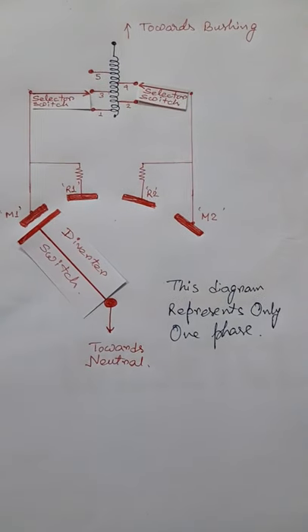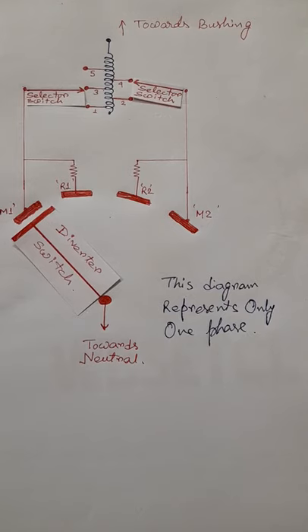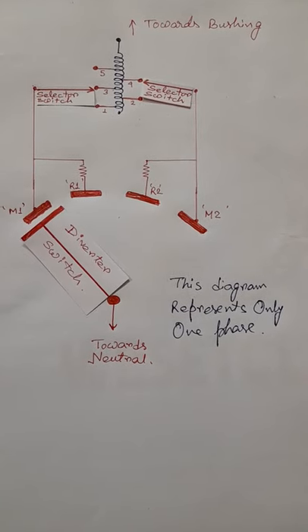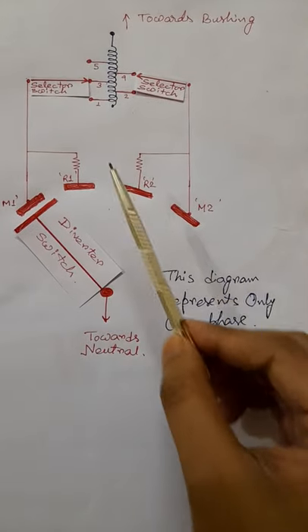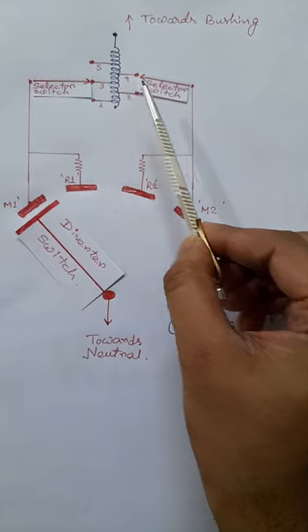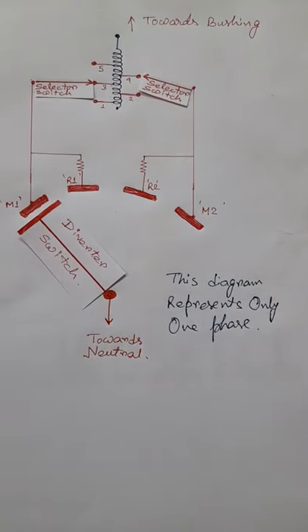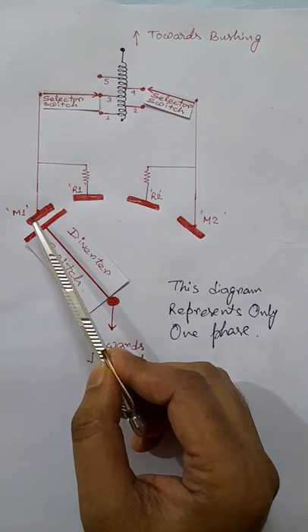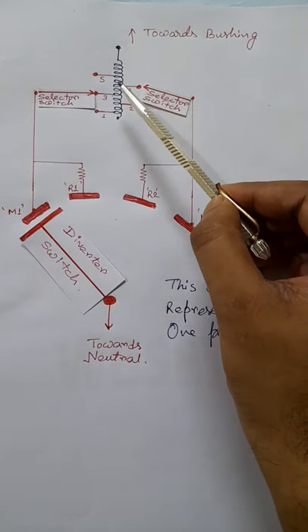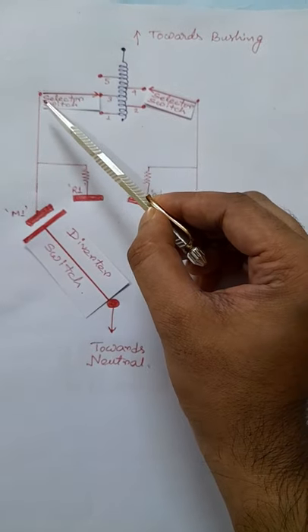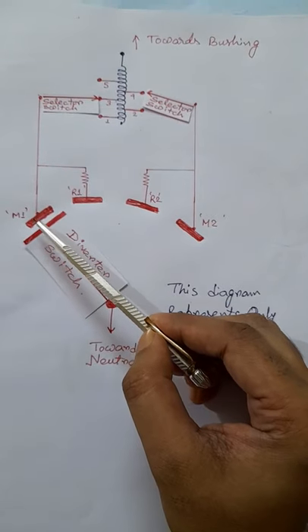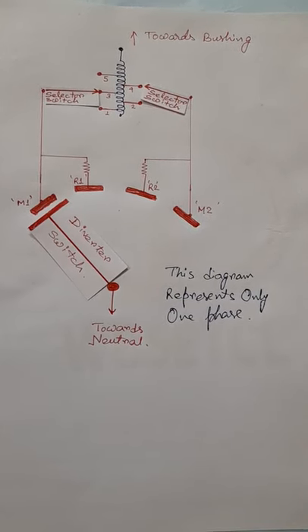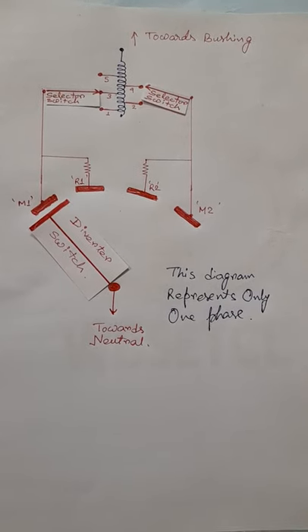In an onload tap changer, two selector switches are used simultaneously for tap changing operation, and this diagram represents only one phase of a three-phase transformer — the other two phases are similar. Notice that one selector switch is connected with tap three and another with tap four. The actual tap position of this transformer is three, because the diverter switch is connected with terminal M1, and the path of load current flows through terminal three, through the selector switch, via M1 and the diverter switch. Though the right-hand side selector switch is connected with tap number four, there is no current flow through it.